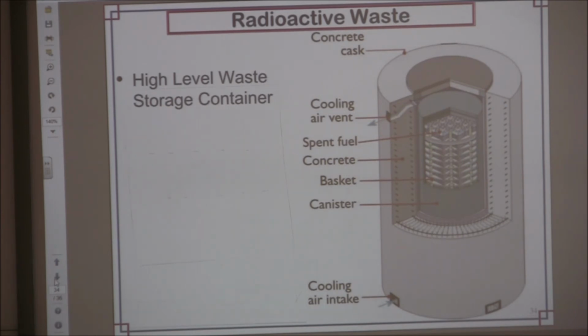So what's the answer today for radioactive waste? You put it in dry cask storage. So you take it out of the spent fuel pool, which is what most reactors have next to them. It's just a pool with water. Water is a great moderator to slow down the neutrons. So you have 20 feet of water over your fuel, and it's essentially no radiation. I've looked down at spent fuel and essentially received no radiation. So it's not radioactive at all once you get through the water. It's a good filter. Lead's really good too because lead's very dense and it's hard for neutrons to sneak through.